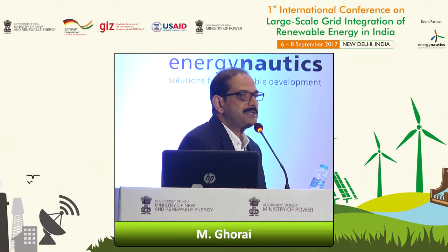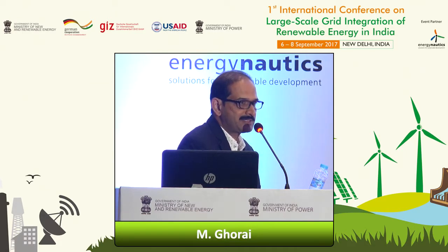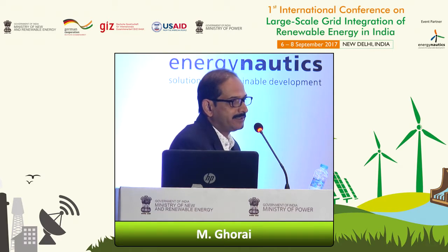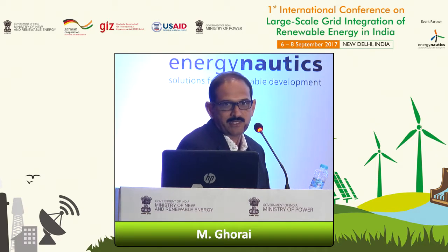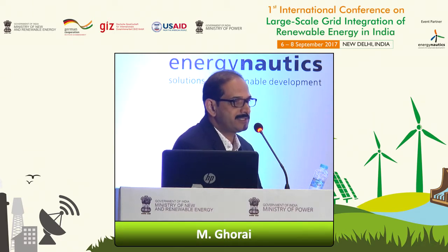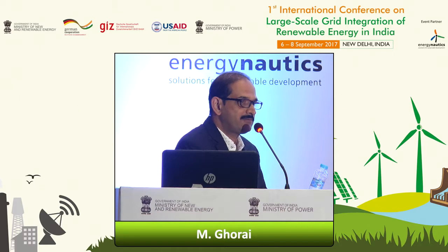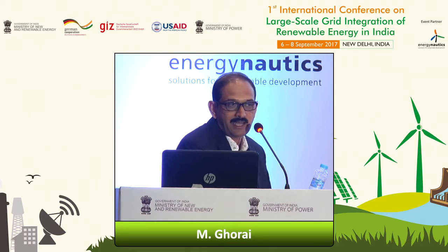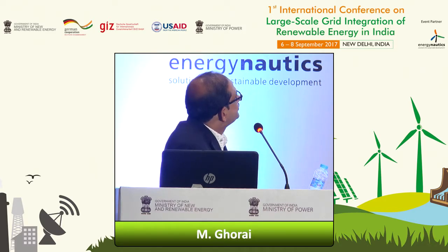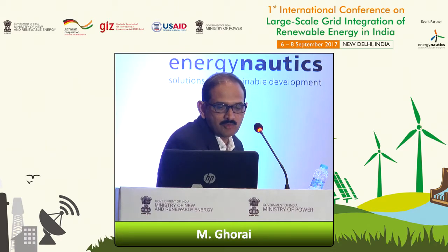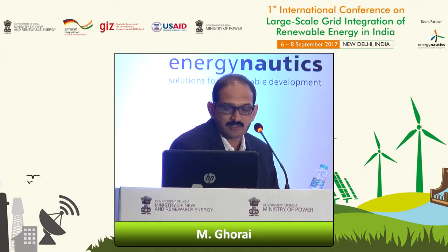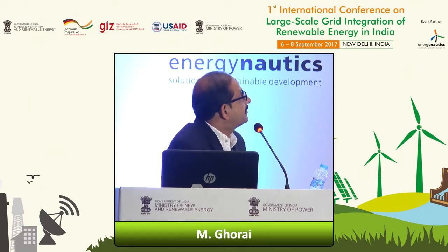South Africa started with renewables very recently, about 4 or 5 years back, and they adopted the grid codes right from day one, in a quite stringent way. They also have a speed of response requirement added to the general grid code requirements. These are the requirements: regulation mode, that is the Q control mode, and power factor control mode. They have given an option of 4% or 8% droop, and a power factor capability of plus or minus 0.95. This is on the regulation side.